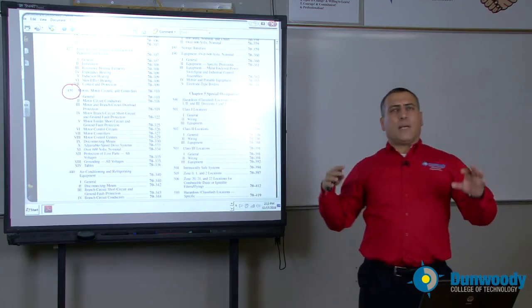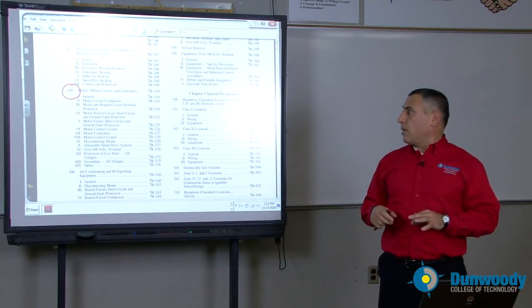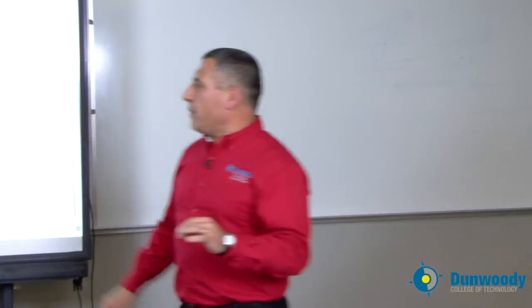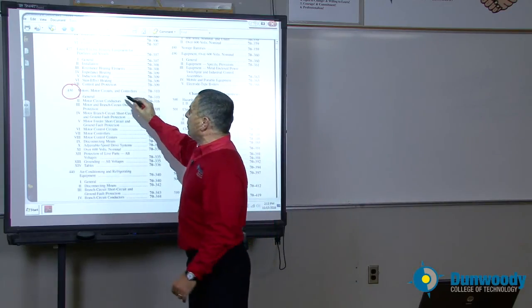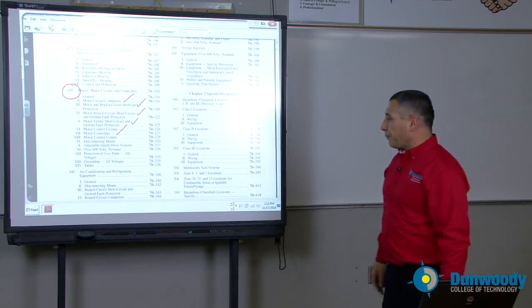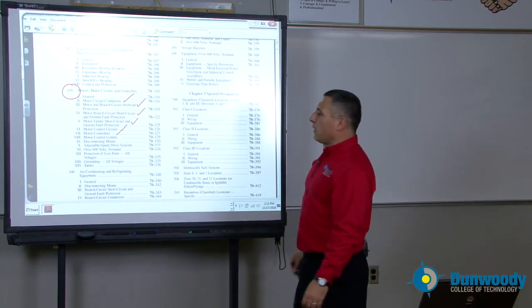The most important article is 430. Every machine that has a motor has to adhere to article 430. How do you size the conductor, the overcurrent protection device, the control circuit, the overload? All this information — from the motor circuit conductor into the overload into the branch circuit, the feeder, the control conductor — will be found directly in article 430.